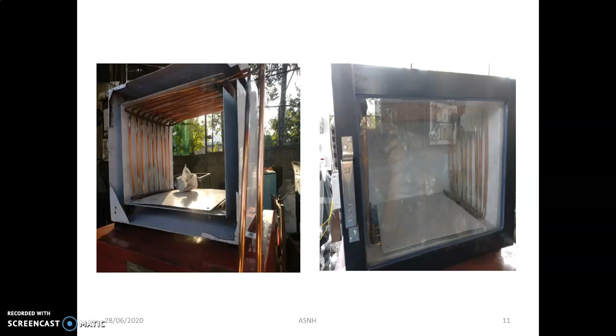Generally in a refrigerator, heat is rejected from the condenser to the atmosphere, but here, instead of the atmosphere, we made a hot box with some cooling coils, and the coils of the condenser reject heat to that hot box. This is the main special arrangement made here to utilize waste heat recovery. We utilize the waste heat from the condenser unit for heating and warming of the food without disturbing the cycle of the refrigeration system. This is the most important thing.